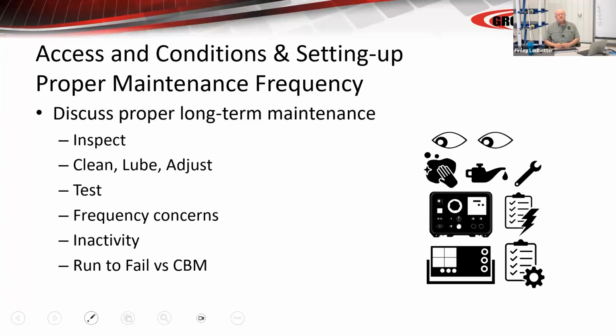So typically, long-term maintenance is inspect the equipment. First, you determine the cycle, determine the frequency, the criticality of the equipment. The parking lot lights, you may not need to test that breaker every year. The primary coolant pump circuit at a nuclear plant, maybe you ought to test it pretty often. So there's some criticality that factors into all this. Then after you do the inspection, there's a clean, lube, and adjust cycle, which is very important. And I've seen just as much damage done by improperly cleaning, lubricating, and adjusting equipment as letting it set. So make sure you have qualified people. There are a lot of technicians that work with a clip jumper and a tweaker screwdriver, but they have no idea how to properly clean, lube, and adjust a low or medium voltage circuit breaker or a protective relay, like an induction disc relay. So be very careful who you allow in to do these clean, lube, and adjust cycles.